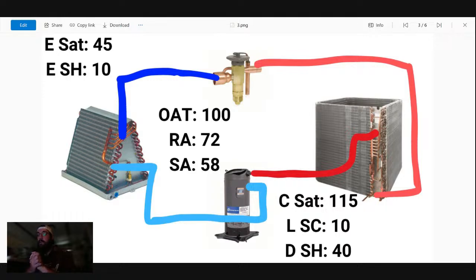Okay, so Brad, outside air infiltration. That's a good one. It could be. For the most part, let's just say this particular unit doesn't have a direct outside air drop or supply line coming into the return. So it's not directly pulling in outside air itself, and there's no gaping holes anywhere. Granted, old windows, bad doors, there's a lot of things that'll cause that infiltration.